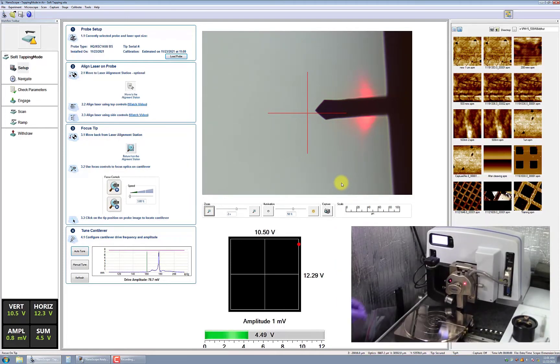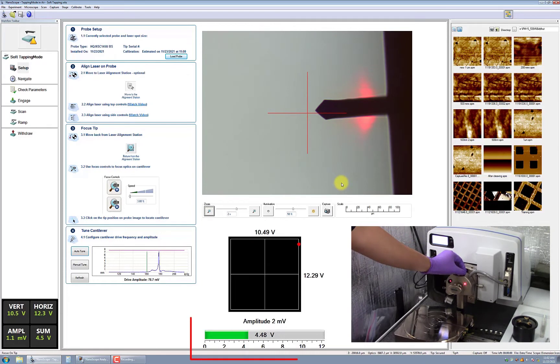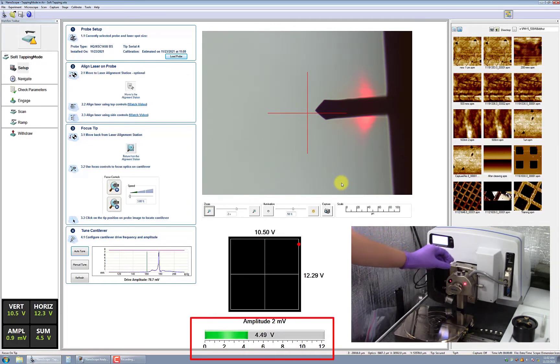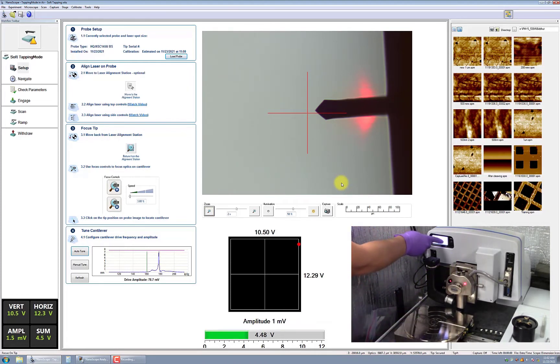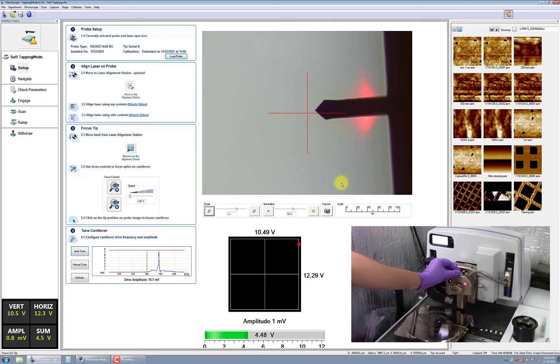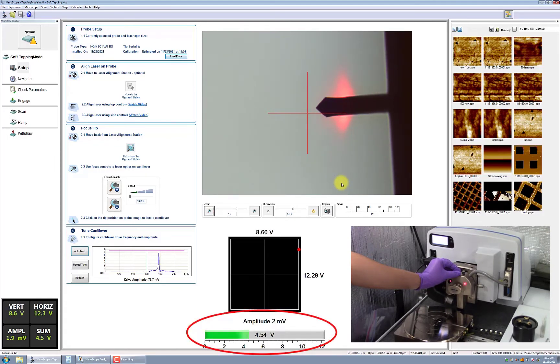Position the laser on the front one-third of the cantilever so that the sum signal is maximized. This is done by adjusting the laser x-direction knob to position the laser at one-third of the cantilever length, and then use the y-direction laser knob to maximize the signal, which should be any value greater than 3 volts, as shown here.